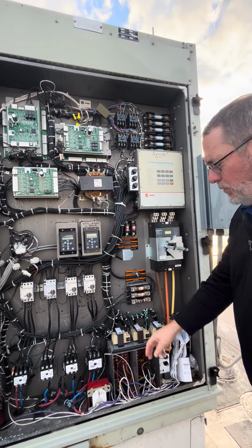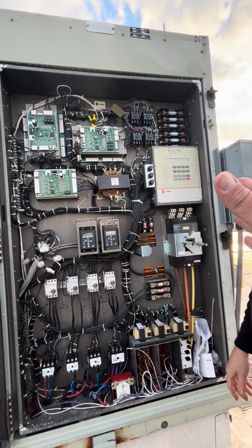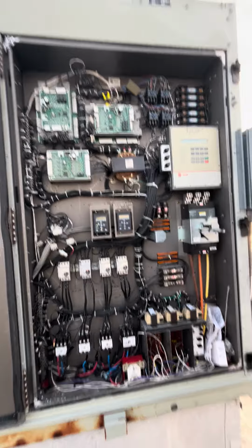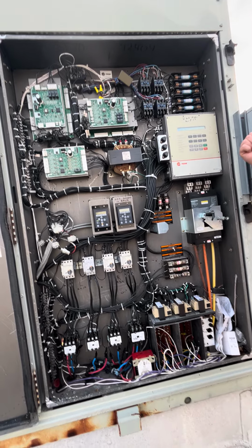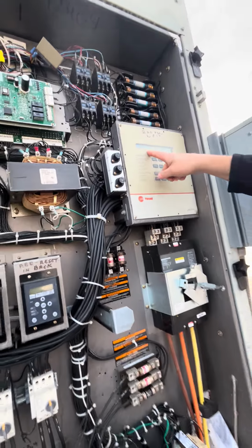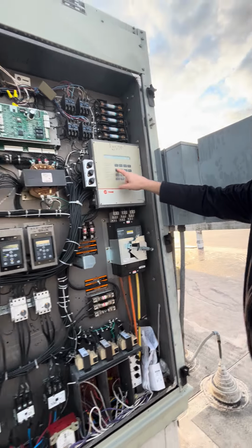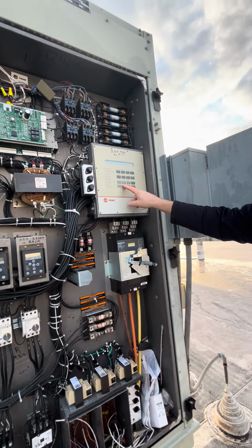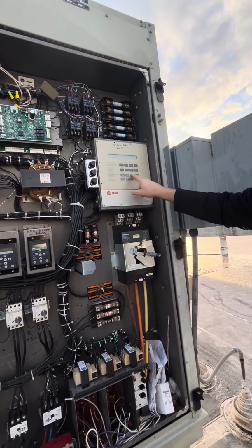When you get a contact closure on TB5 1 to 2, it locks out cooling. So if this is at 50%, you lock out half. That could be why we're sometimes wondering what's wrong, why we're not running all the compressors, if someone set it for 50 and that contact is closed. But you're saying this is 100? This one's 100. Okay. So we probably need to investigate that. That's under the setup. I would hope that they just leave it at 100. Right there, you can go, there's your 0, 50, and 100. There's your 3 options. All right, that makes sense.